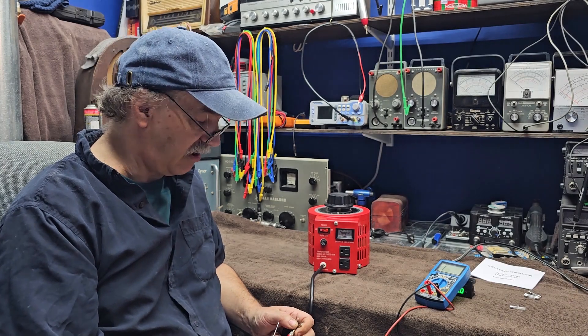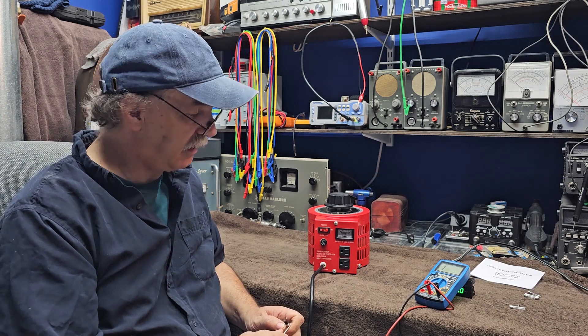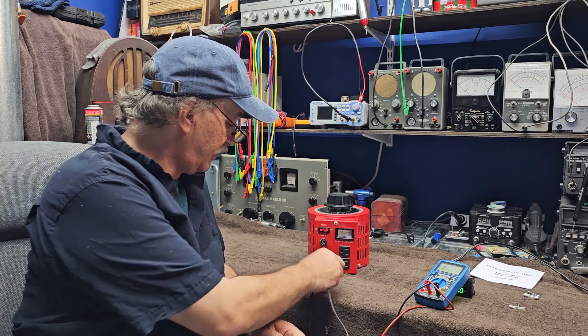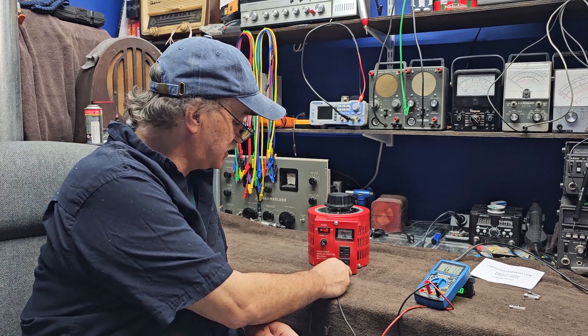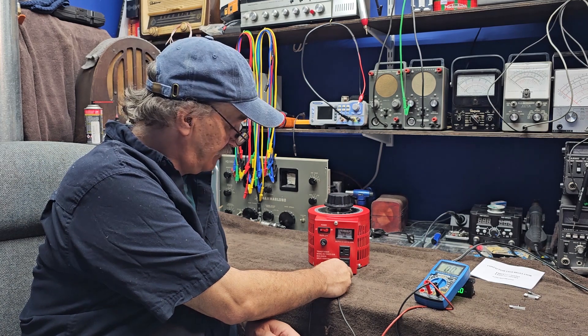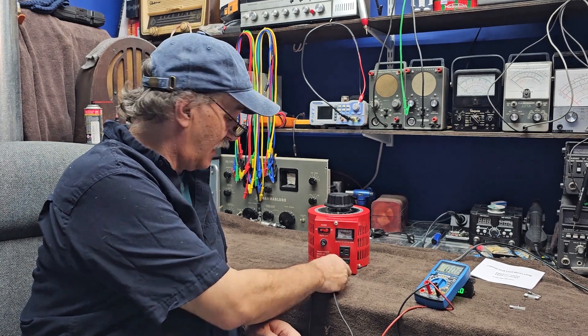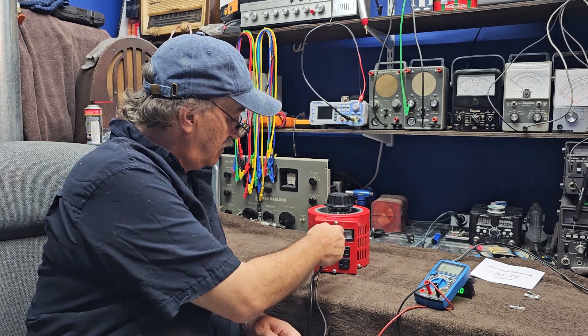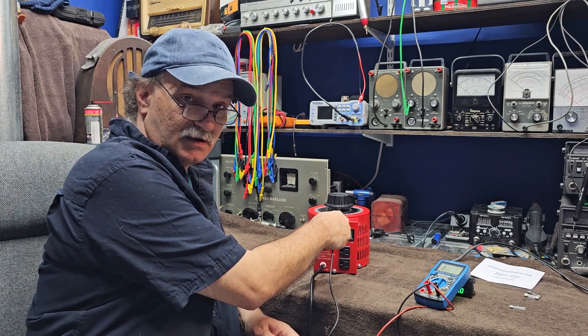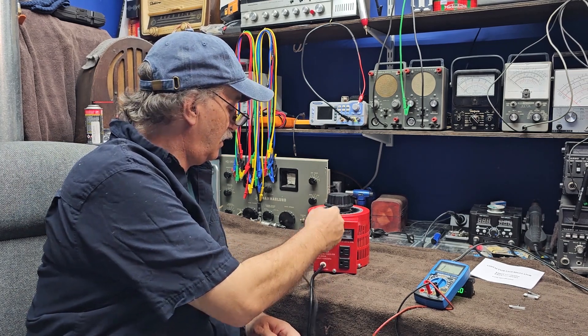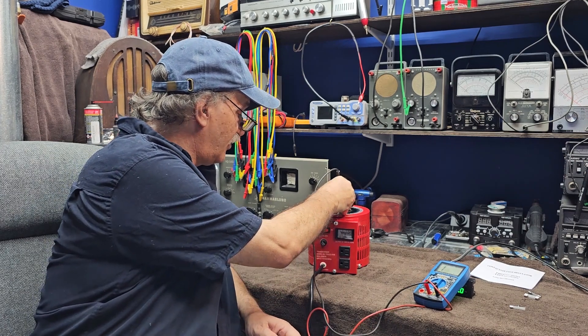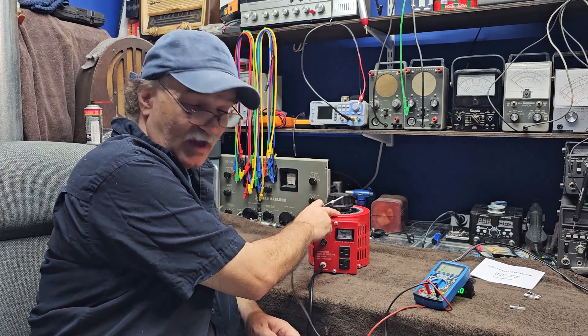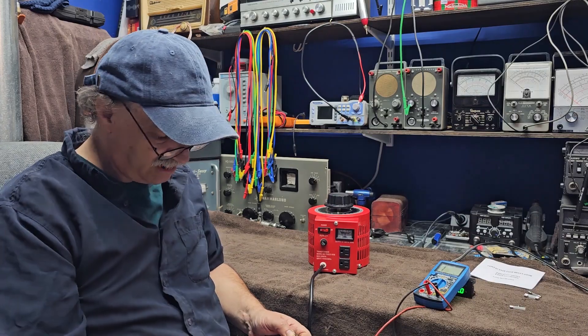Okay we're set up with a basic continuity meter. If we check on this screw here we have continuity which tells me that the case is bonded at that point, there's a screw on the side here which seems good, the screw on the top nothing that's a problem, that goes into this top panel here and here's another screw on the top nothing. So that tells me this top panel is not bonded to ground that we're going to have to correct so that's kind of important.